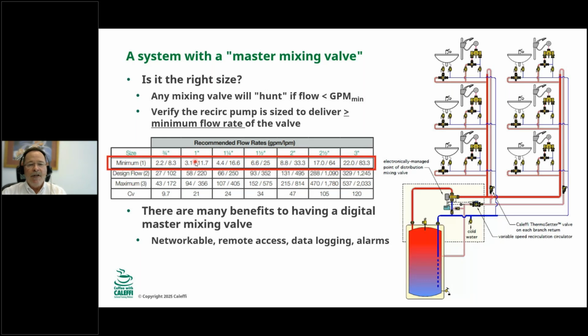Now, digital valves, which are more commercial, like in this schematic here, are more expensive, but they have a lot of benefits, especially in commercial applications. You can network them, you can have remote access, you can read and write set points to them, you can get data logging and alarms. They're gaining in popularity very quickly. And we highly recommend looking at digital master mixing valves whenever you're in a commercial application.